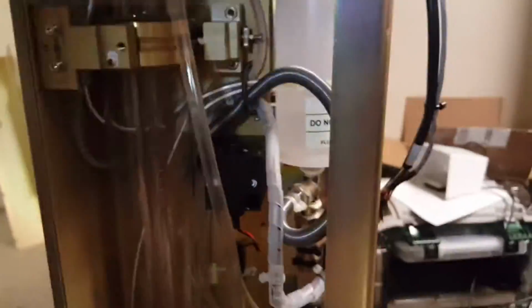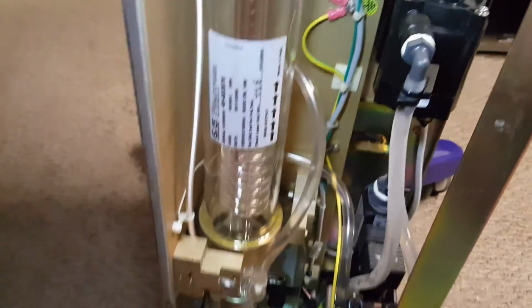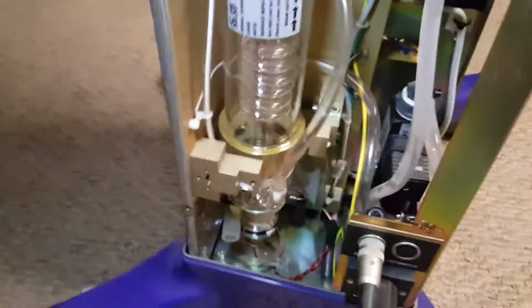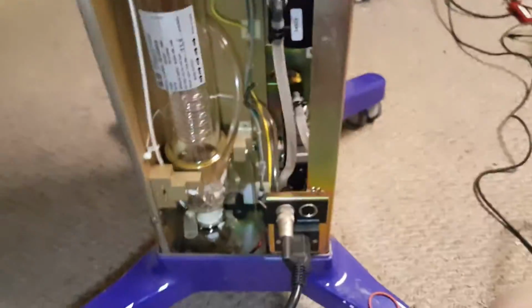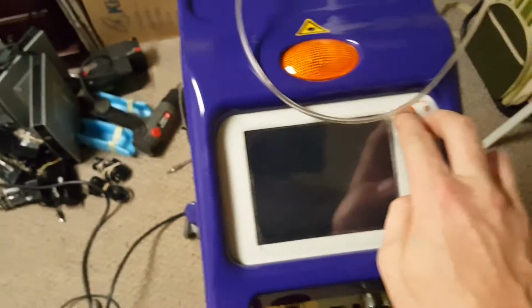And so even if the laser is on, it's dumping the beam until you depress the foot pedal, at which point it opens the shutter and then the beam goes through the laser and onto the subject. So that's how that senses power, and what I needed to do was test that. And so how do we test that? Well, it turns out it's actually really easy. So I'm going to boot this up into the service menu, put you down for a second.